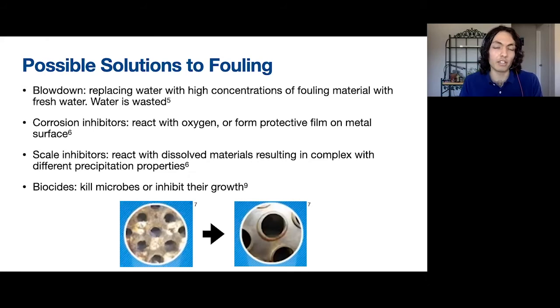To prevent scaling, we could also use scale inhibitors, chemicals that react with those dissolved salts in the water and result in new compounds with different precipitation properties. What I mean is that the temperature at which they become supersaturated is different — not a temperature found within the cooling system. That way we avoid scaling formation.